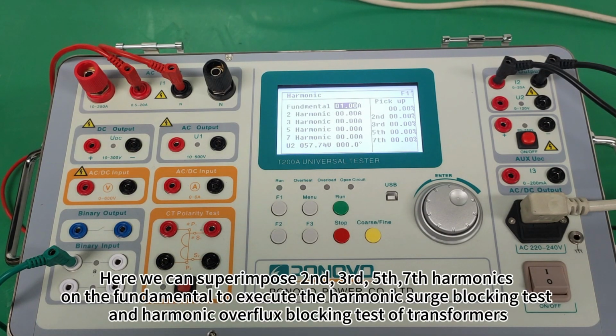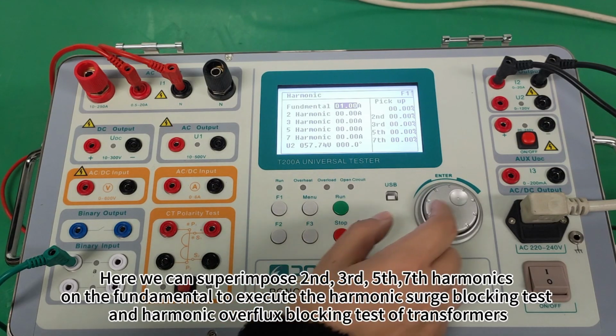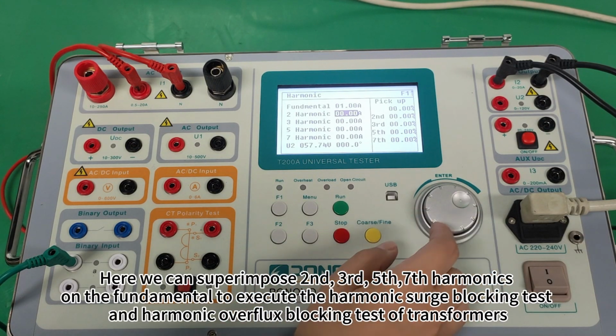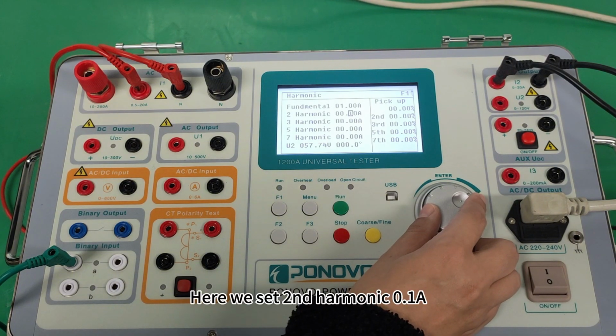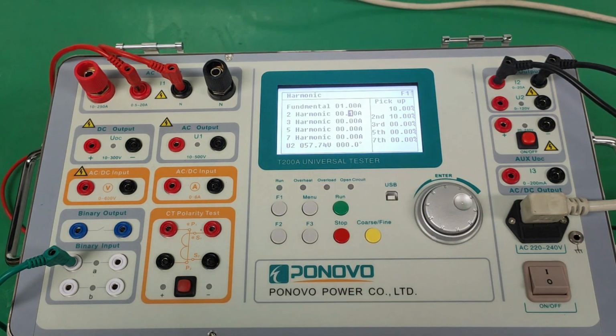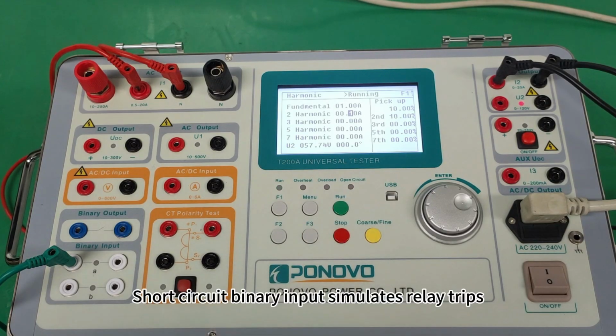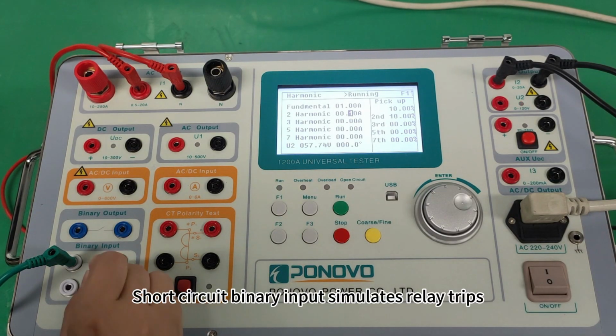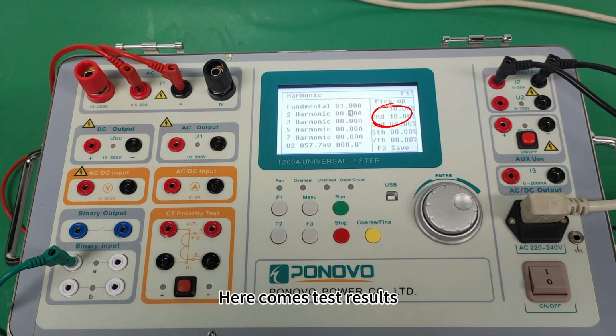Next, harmonic test. Here we can superimpose second, third, fifth, seventh harmonics on the fundamental to execute the harmonic surge blocking test and harmonic overflux blocking test of transformers. Here we set second harmonic 0.1 ampere. Press Run button. Short circuit binary input simulates relay trips. Here come test results.